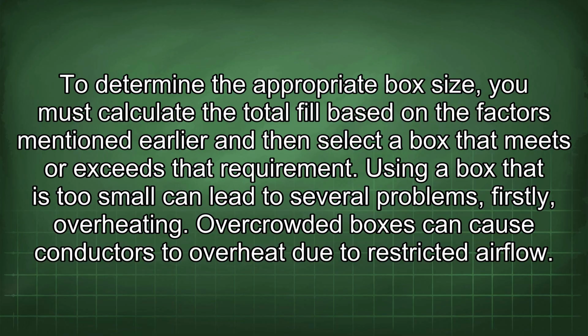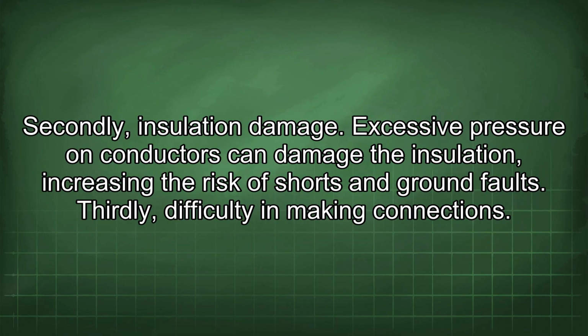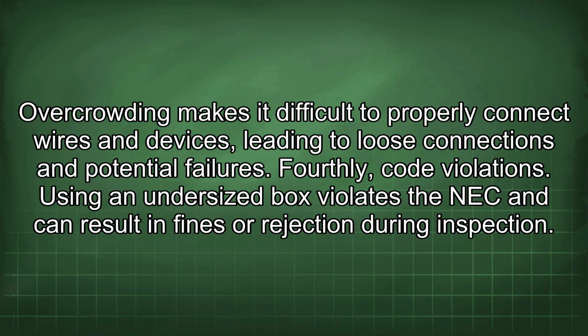Using a box that is too small can lead to several problems. Firstly, overheating. Overcrowded boxes can cause conductors to overheat due to restricted airflow. Secondly, insulation damage. Excessive pressure on conductors can damage the insulation, increasing the risk of shorts and ground faults. Thirdly, difficulty in making connections. Overcrowding makes it difficult to properly connect wires and devices, leading to loose connections and potential failures. Fourthly, code violations. Using an undersized box violates the NEC and can result in fines or rejection during inspection.